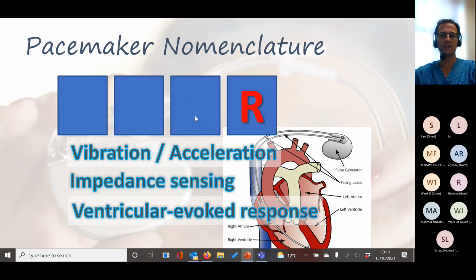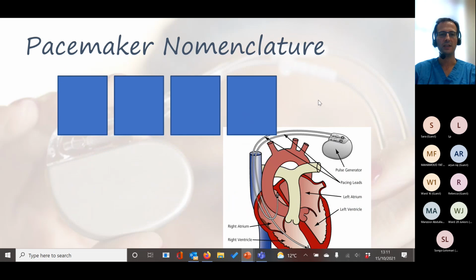So normally it might just be set up listening to how fast the atrium wants to go, but you might have to set it so that it can respond. And that's where the fourth letter comes in. So that's why we call pacemakers AAIR or VVIR or DDD. Don't worry if that didn't make too much sense, but hopefully you can see the difference between a single chamber and a dual chamber pacemaker.